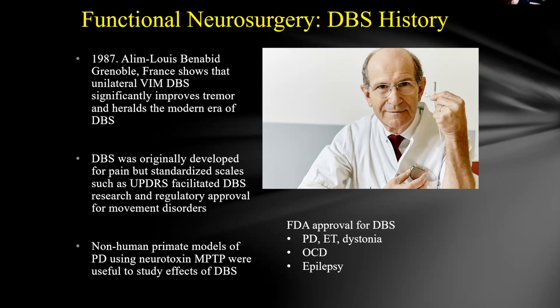The limitation of unilateral placement was that about 20% of fibers cross over, so full benefit requires bilateral stimulation — and essential tremor is typically a bilateral progressive disease. Within about two more years, DBS received FDA approval for bilateral placement and subthalamic placement for Parkinson's disease. By 2001, it received a Humanitarian Device Exemption for dystonia, requiring an FDA-sponsored institutional study.